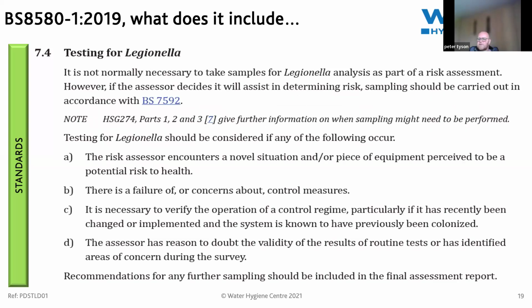What about testing for Legionella? Well, testing for Legionella is not a prerequisite for a Legionella risk assessment. They are included as a bit of a money spinner in our opinion. British Standard 8580 details clearly when a sample might want to be taken as part of that risk assessment, and British Standard 7592 details how to take a Legionella sample, pre and post flush, and the technique. So sampling at the time of a risk assessment is often just add-on costs - it's not a prerequisite, doesn't need to be done. I think it sometimes takes a little bit away from the actual risk assessment, because they've got to go and take the samples correctly, drop them off at the laboratory, and it's all time that could be better spent, in my opinion, actually assessing the risk in more detail.